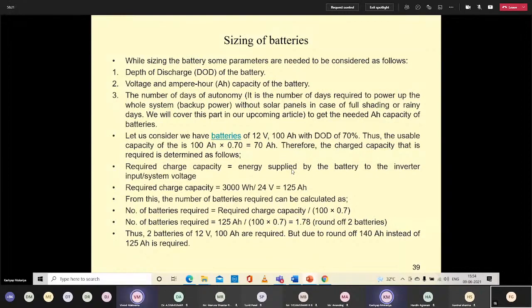So number of batteries required is equal to required charge capacity divided by 100 into DOD. So it comes at 125 ampere hour divided by 100 into 0.7, so 1.78. By rounding, you get 2 batteries. So 2 batteries of 12 volt 100 ampere hour are required, but due to round off, you have to go with some higher factor. You should not go with 125 ampere hour; you should go one step higher. We can go for 140 ampere hour instead of this.